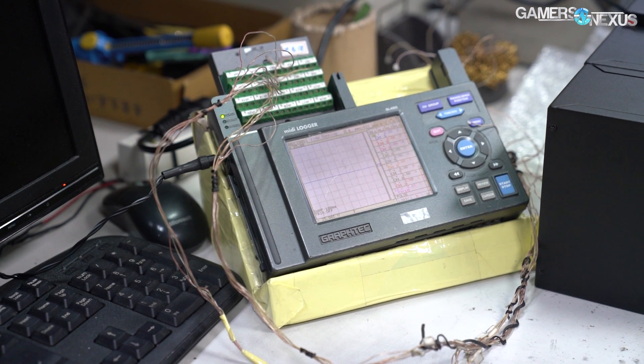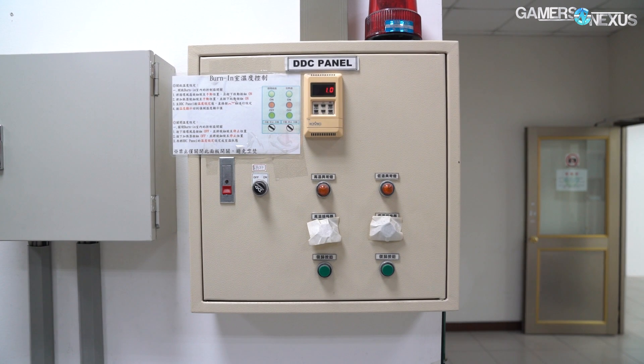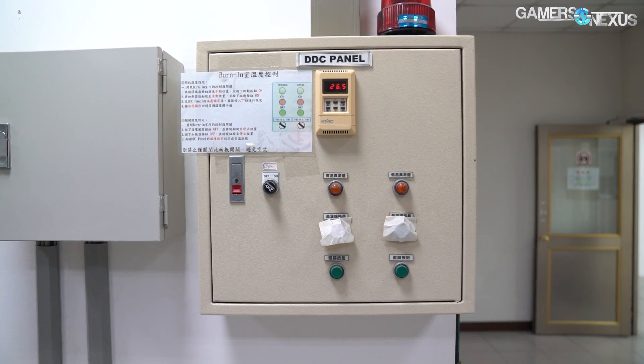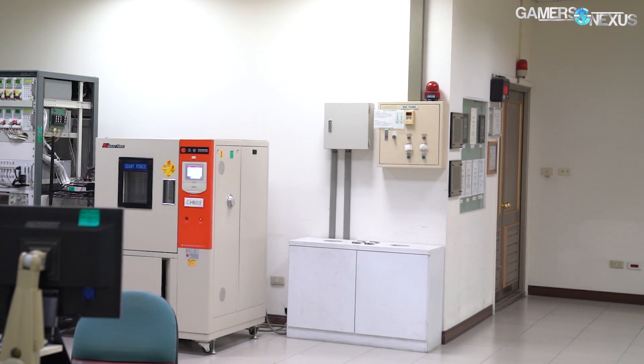The thermocouple readers are wired up again with 40 to 100 probes from the power supply's internal components, then logged for data analysis later. With 48 hours of data per device, there are potentially millions of lines of data to align against load generation, ambient temperature, and humidity in the charting software. Mounted to a wall is a DDC panel for a burn-in testing room that's been converted into a warehouse for storage space.